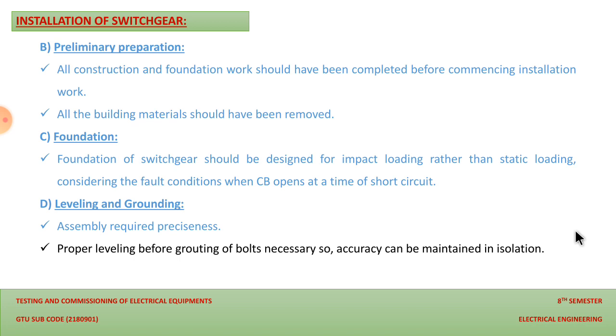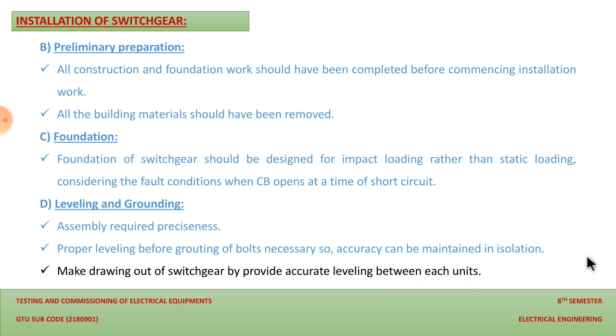So yes, we have a bolting structure on the plinth of the structure where we are installing our switchgear. So proper bolting must be there, so that we can properly tighten our instrument for future operation, and we can protect our device from further vibrations during the operation. Make drawing out of switchgear by providing accurate leveling between each unit. So this is necessary for the smooth operation of the switchgear.